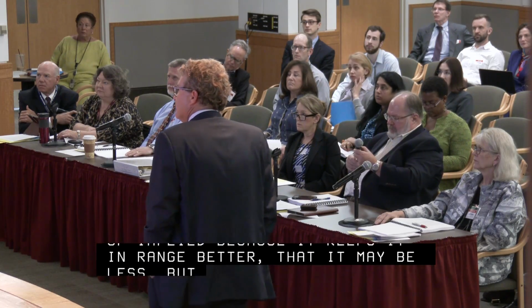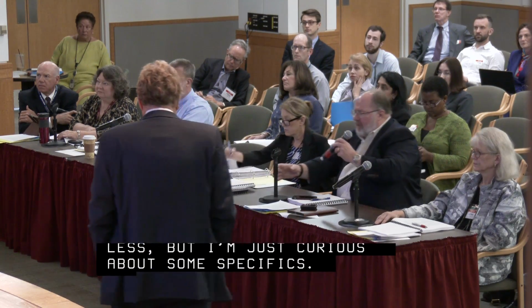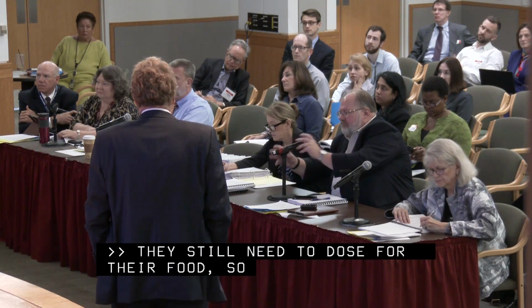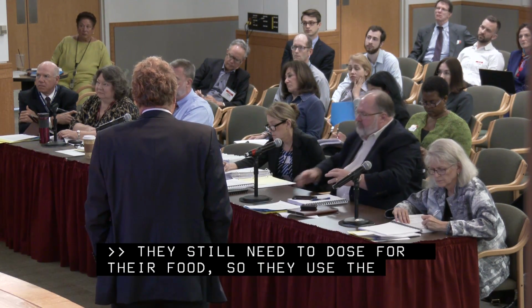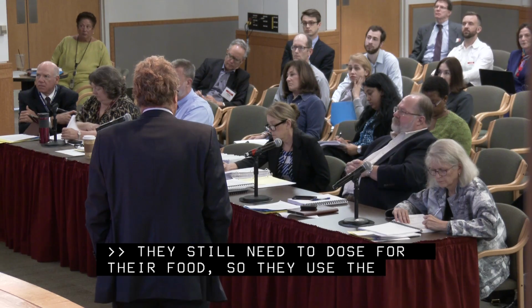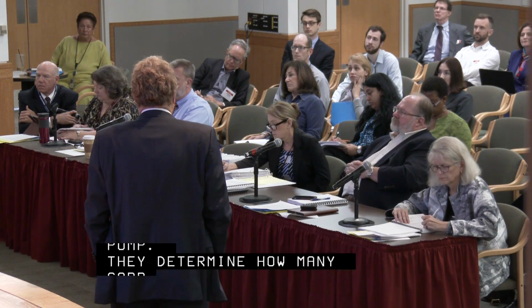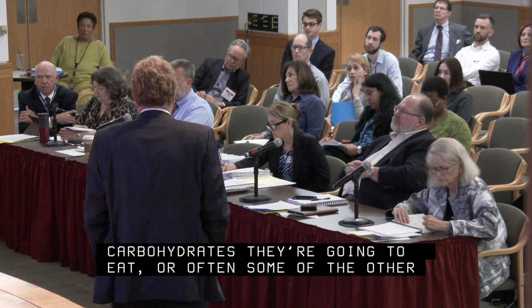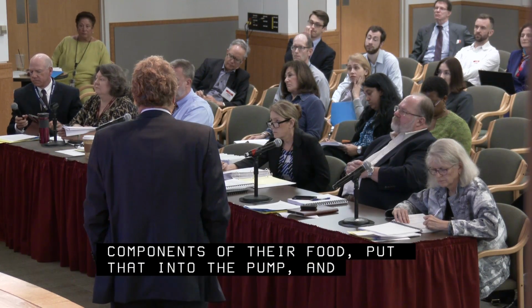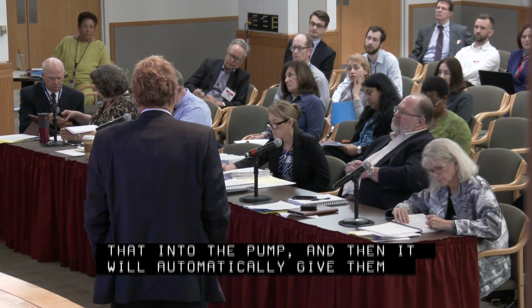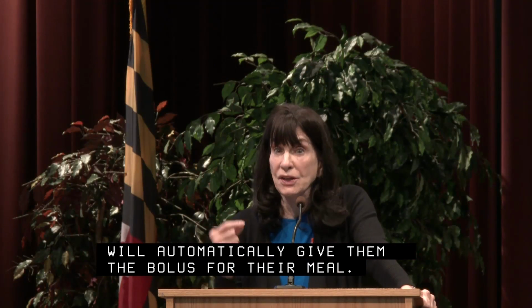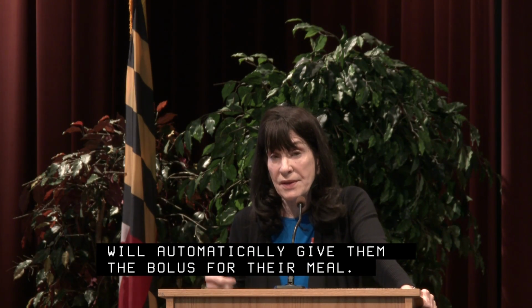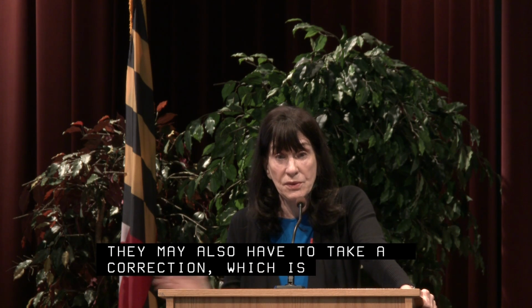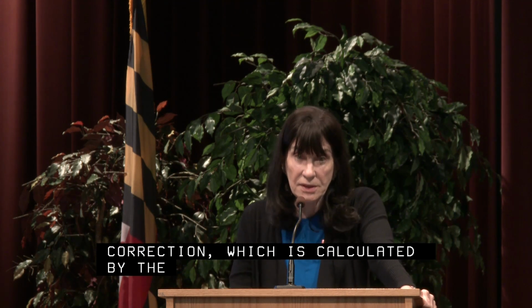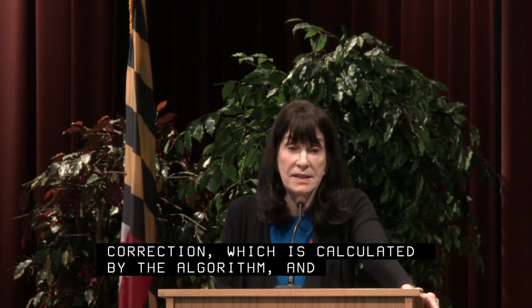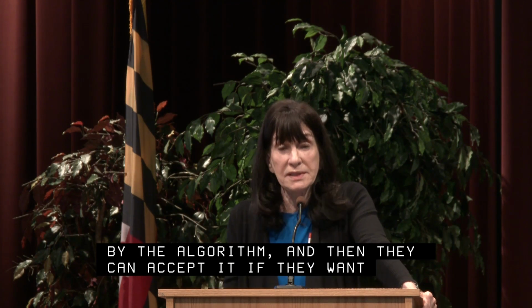They still need to dose for their food, so they use the bolus calculator inside the pump. They determine how many carbohydrates they're going to eat, or often some of the other components of their food, put that into the pump, and then it will automatically give them the bolus for their meal. They may also have to take a correction which is calculated by the algorithm, and then they can accept that if they want to, or not take an additional correction dose of insulin as a bolus. Most of the time they will take it.